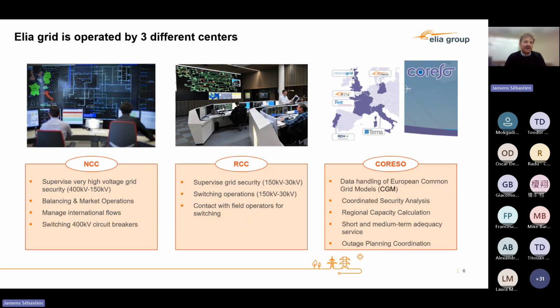Let's dig into the operators. We have 3 different levels in Belgium. The first is the NCC, the National Control Center, located in Brussels. They supervise the very high voltage grid security, handling switching from 400 kV down to 150 kV, but not the whole 150 kV grid. They handle the main flux lines, are in charge of balancing and market operations, manage international flows, and switch all the very high voltage gear.